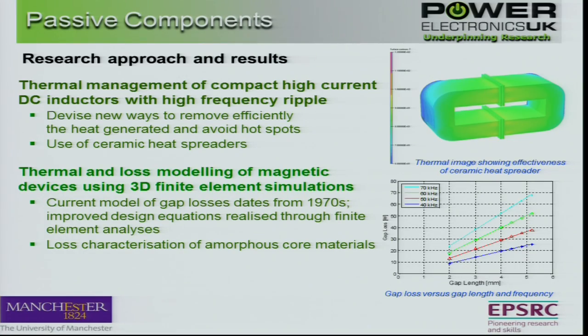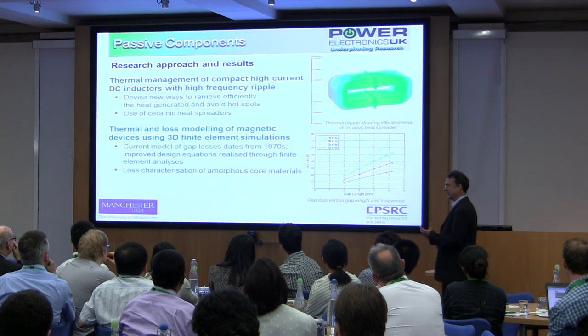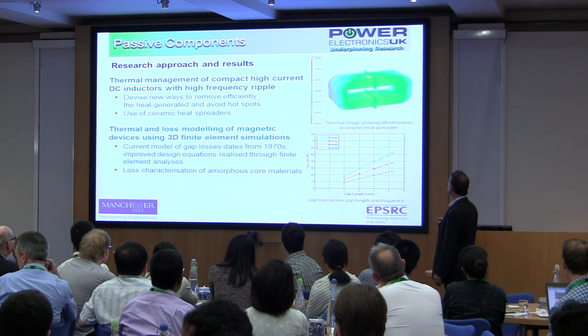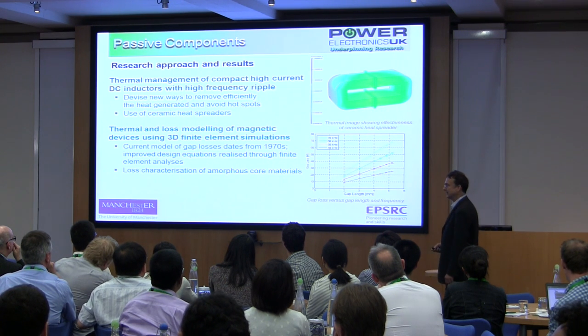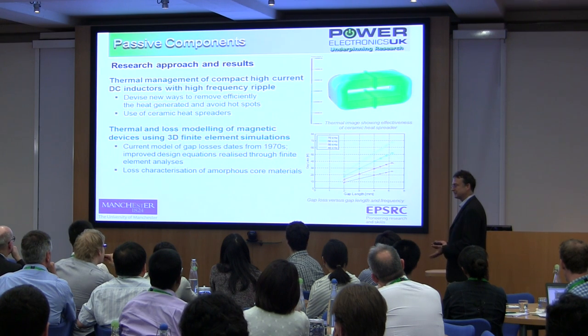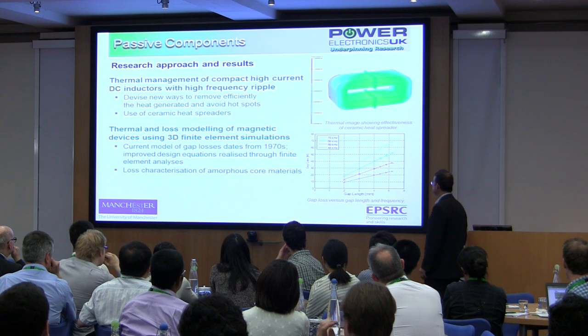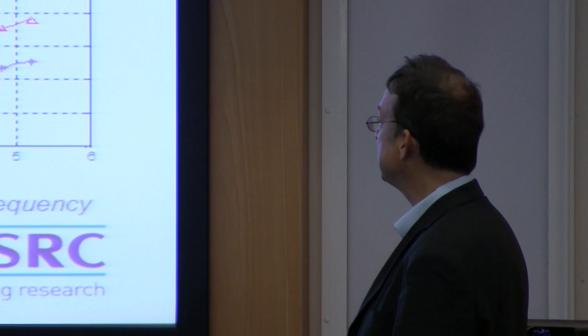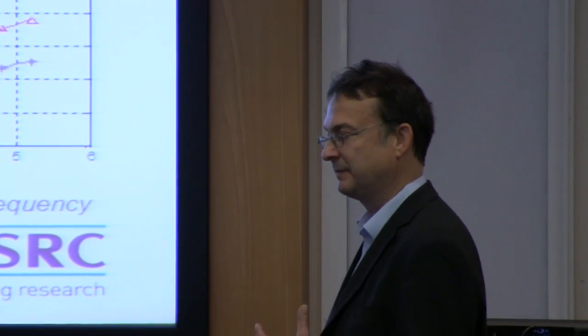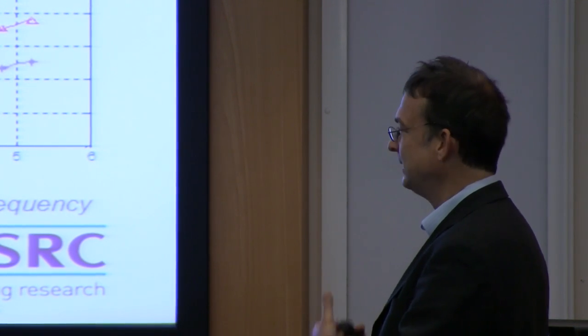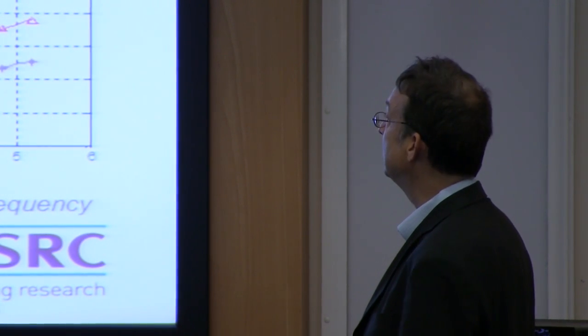Here are some results on the work that Manchester will be looking at in terms of improving the thermal management of a wound component. If you've got a core with an air gap, you get nasty fringing fluxes around the air gap — those cause localised heating in the lamination and in conductors sitting around there. You can mitigate that through various means; one way is to put heat spreaders in, which calms down the temperature gradient within the device. The other diagram shows the variation in gap loss versus gap length and operating frequency, looking at techniques of reducing that through modelling and finding new ways to reduce the problem, potentially incorporating new magnetic materials in these wound components.